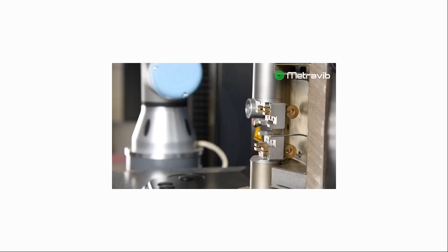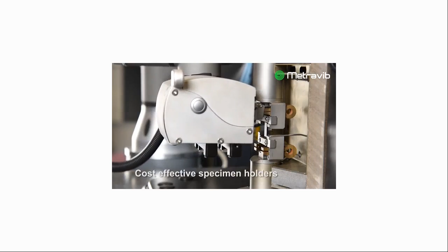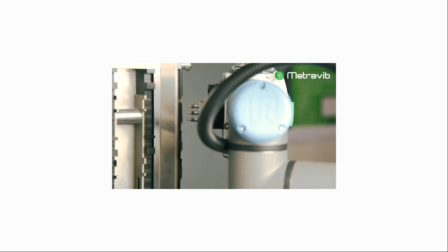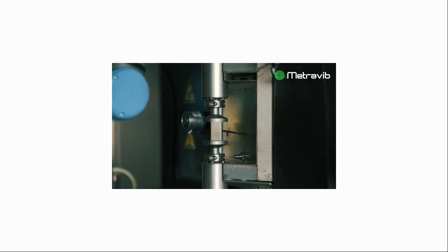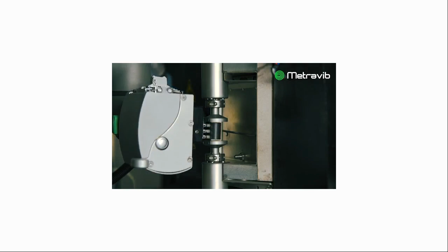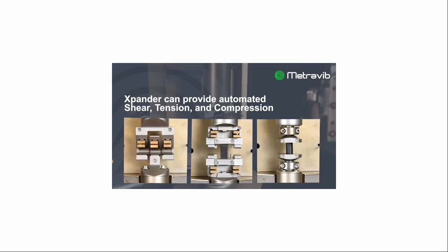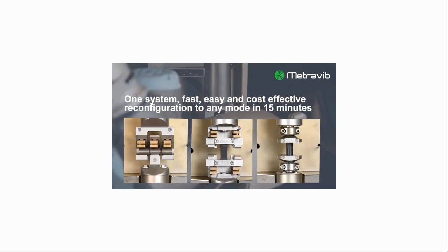So you can see here a tension mode test campaign. The principle of the gripping system is the same. We use a vacuum cap, and here we use a spring, a high stiffness spring, to ensure the clamping of the system. The robot rotates the magazine to change the rack, and you can see how the system grips the compression test directly on the rubber with the vacuum cap. This is a large dimension specimen, but here with a very small dimension specimen, 5 millimeter, we also have the same capabilities. You can see how flexible the system is and how easy it is to load the specimen in the magazine.